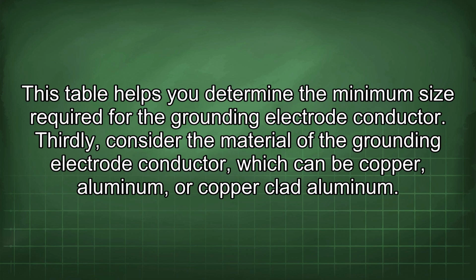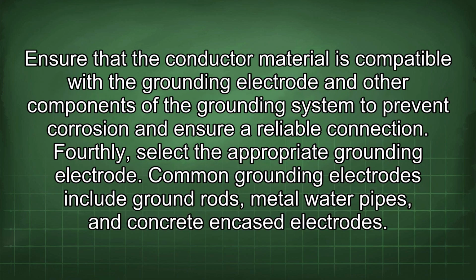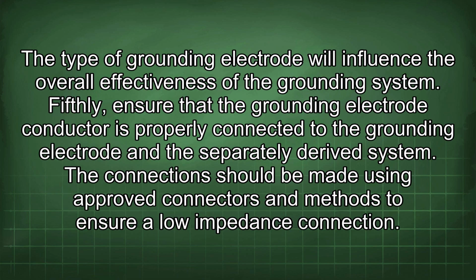Thirdly, consider the material of the grounding electrode conductor, which can be copper, aluminum, or copper-clad aluminum. Ensure that the conductor material is compatible with the grounding electrode and other components of the grounding system to prevent corrosion and ensure a reliable connection. Fourthly, select the appropriate grounding electrode. Common grounding electrodes include ground rods, metal water pipes, and concrete encased electrodes. The type of grounding electrode will influence the overall effectiveness of the grounding system.